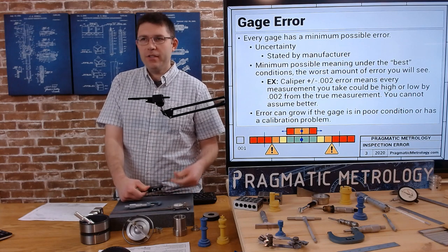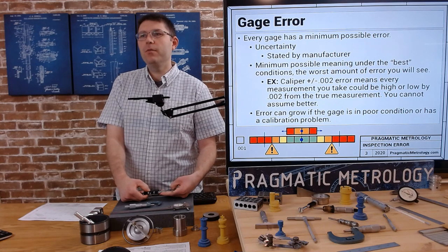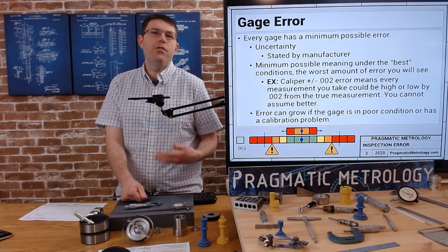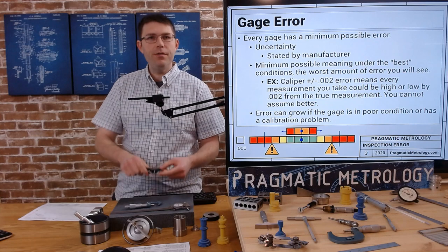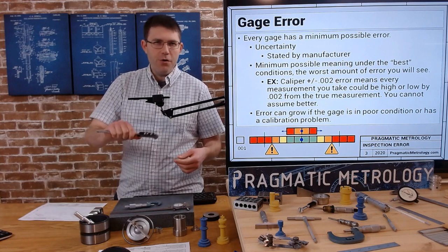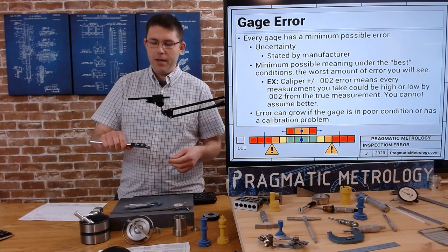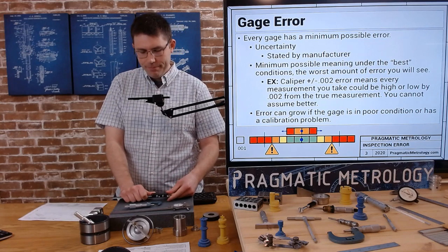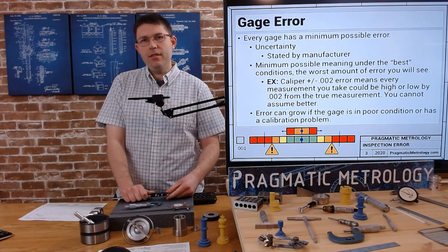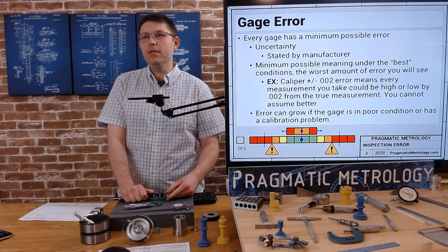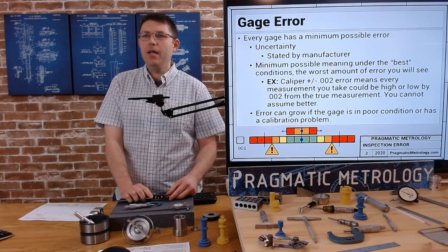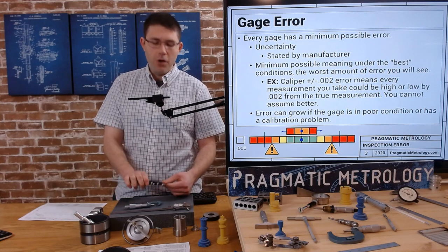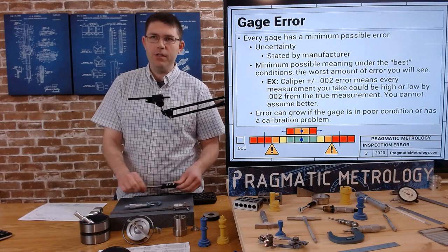For example, this caliper plus or minus 2 thousandths error means every measurement you take could be high or low by 2 thousandths from the true measurement. You can't assume better. Even if you think you've really used this caliper, you know this caliper, you've used it for years - you can't rely on that as a scientific way of determining the accuracy. Error can grow if the gauge is in poor condition or has a calibration problem. You've got to verify the gauge is in good enough condition to reach that level.